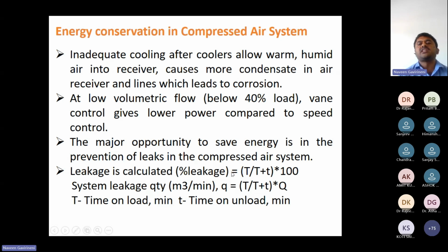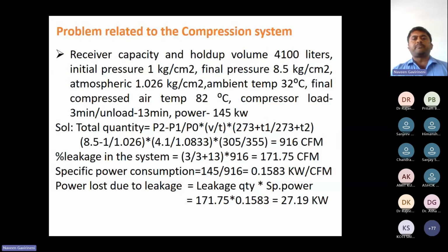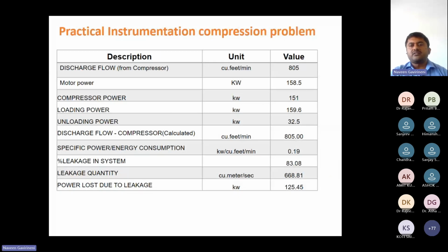So this is the leakage calculation: T divided by T plus t, into 100, where T is the time of load and t is the time of unload. If you do not have the time provision, you can take the loading pressure and unloading pressure also. So this is the practical problem. Due to lack of time, while sharing this PPT, just go through that. These are the end results: discharge flow, motor power, compressor power. Finally, we are getting a power loss of 125 kilowatts like that. While going through that, you will be able to know.